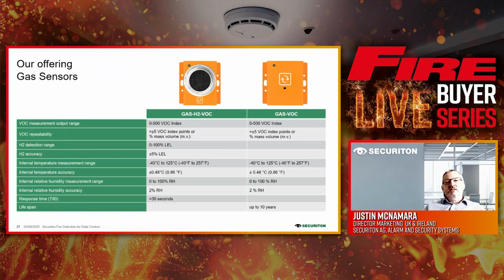The last thing we want is something like a battery to cause potential problems for the server room next door or server plant above. These sensors are finely tuned to detect that almost pre-alarm warning of a battery going into thermal runaway before it gets into fire and anything worse. So they are a great addition to Securiton's range, and dare I say it, a great addition to any data center wishing to provide the highest level of detection.